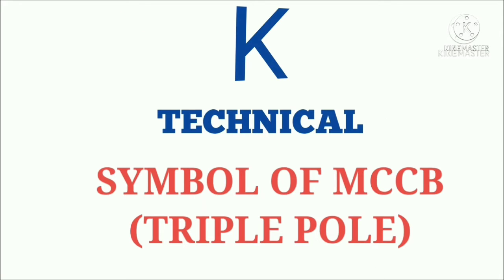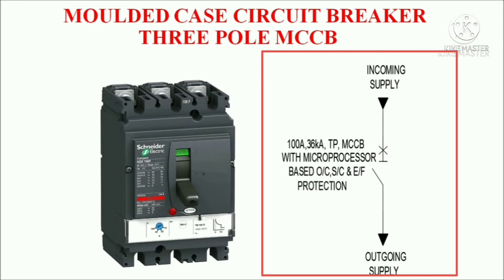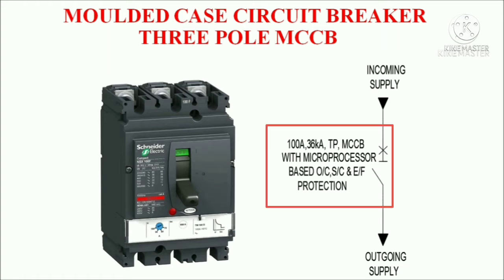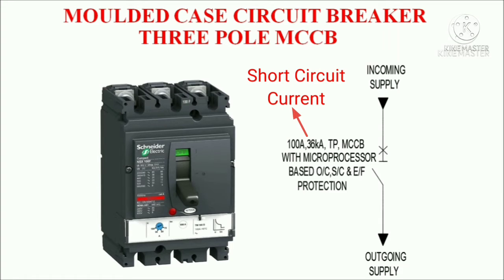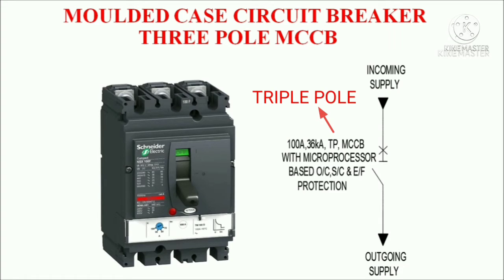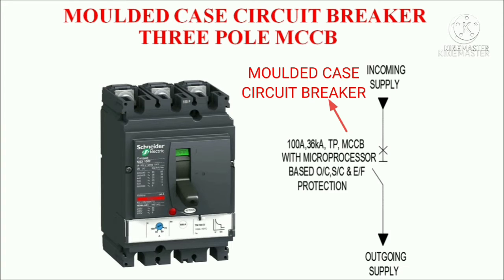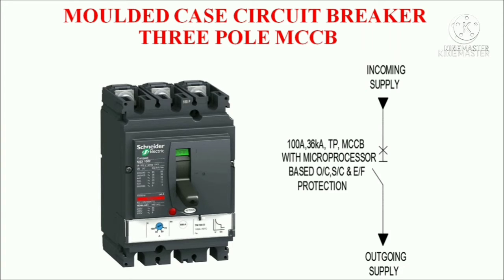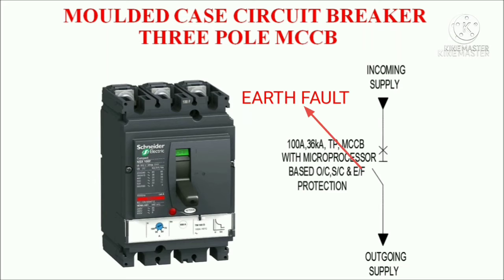Now let's talk about MCCB — moulded case circuit breaker. The symbol of 3 pole MCCB is shown here. You have to write the rating like this: 100 Ampere current rating, 36 is short circuit rating, TP means 3 pole. MCCB with microprocessor has two types of protections: one with microprocessor and another with thermal magnetic — covering over current, short circuit, and earth fault protection.